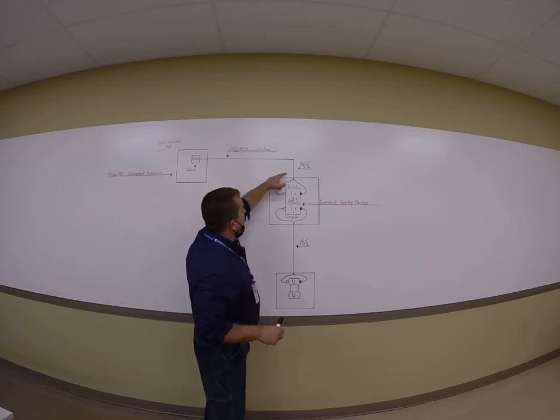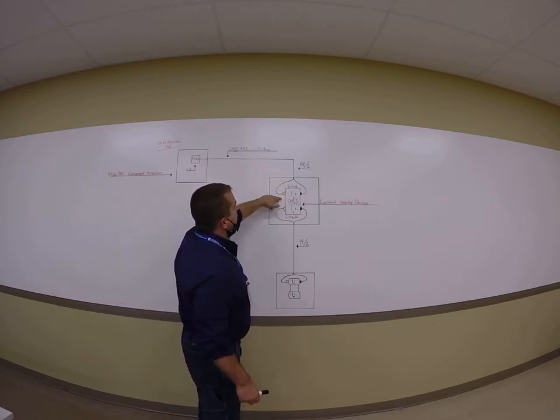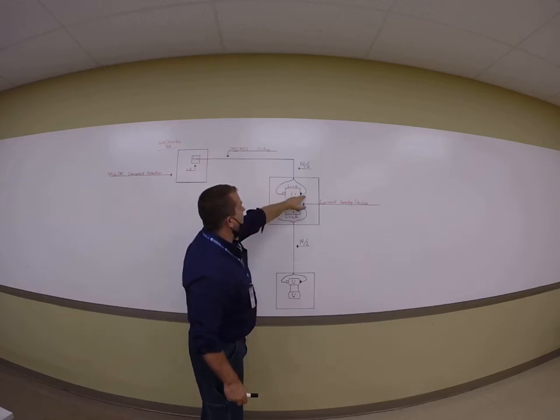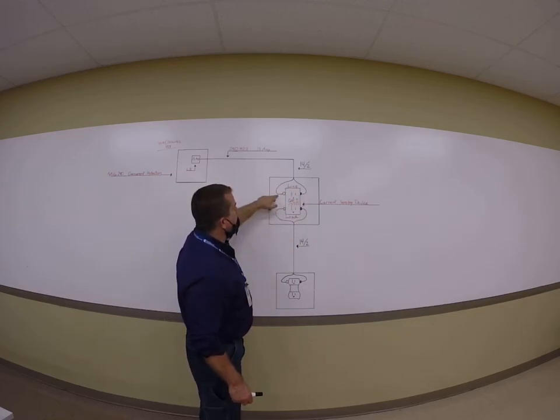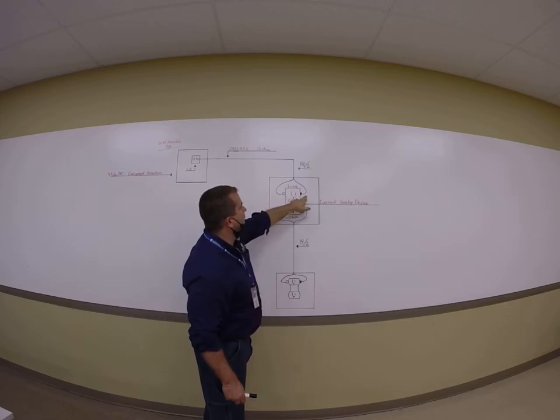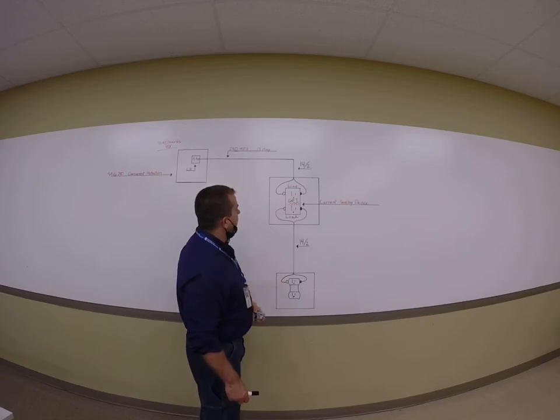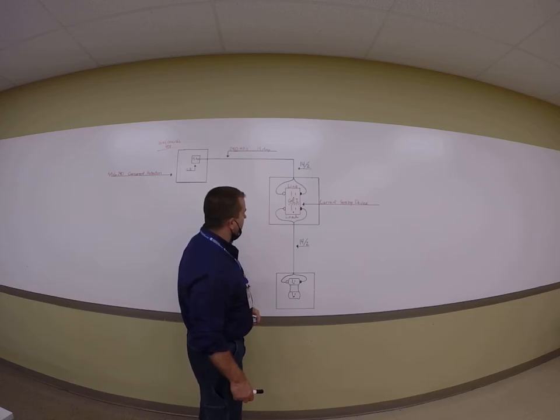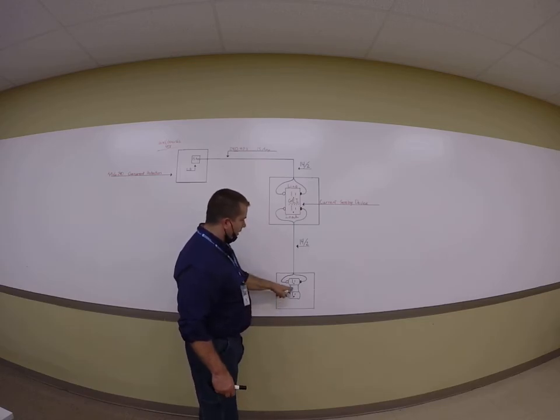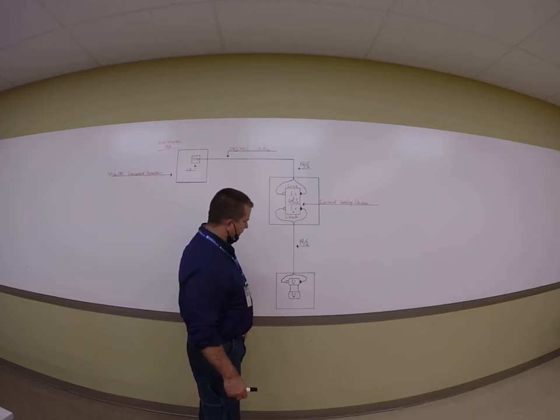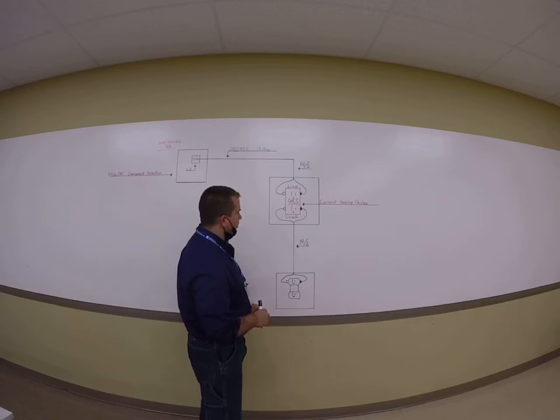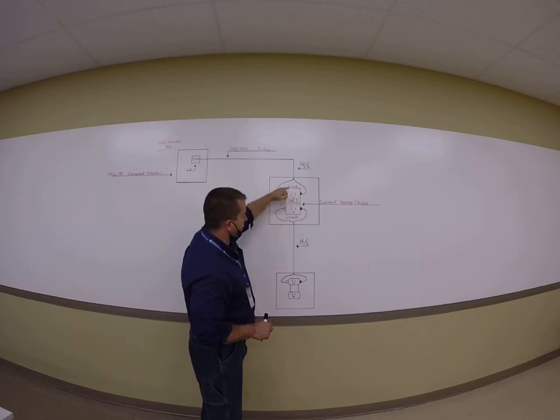So what I want to present and explain more thoroughly is, if you're looking at my drawing right here, the wire that comes from the panel that comes into that GFI, the feed has to tie into the line. So I use blue to represent the white wire, black to represent the black wire with the brass screw being the black dot. And then anything that I want to be controlled by the GFCI is on the load side. So let's say I plug in a piece of equipment down on this regular receptacle. Plug it in. Now that piece of equipment is ground fault circuit protected. That load has to physically go through this device.